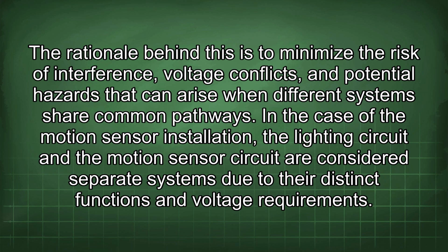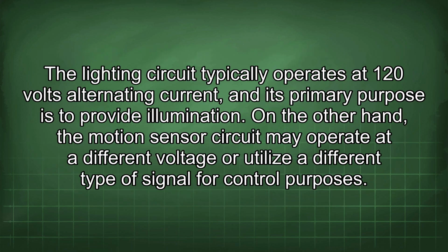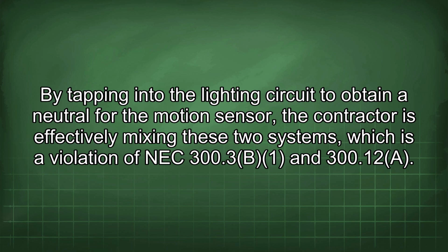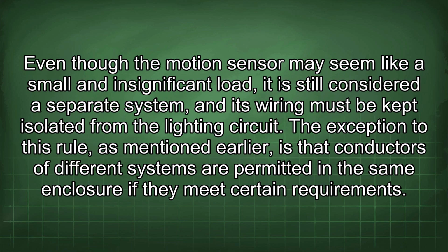In the case of the motion sensor installation, the lighting circuit and the motion sensor circuit are considered separate systems due to their distinct functions and voltage requirements. The lighting circuit typically operates at 120 volts alternating current, and its primary purpose is to provide illumination. On the other hand, the motion sensor circuit may operate at a different voltage or utilize a different type of signal for control purposes. By tapping into the lighting circuit to obtain a neutral for the motion sensor, the contractor is effectively mixing these two systems, which is a violation of NEC 300.3(B) and 300.12(A). Even though the motion sensor may seem like a small and insignificant load, it is still considered a separate system, and its wiring must be kept isolated from the lighting circuit.